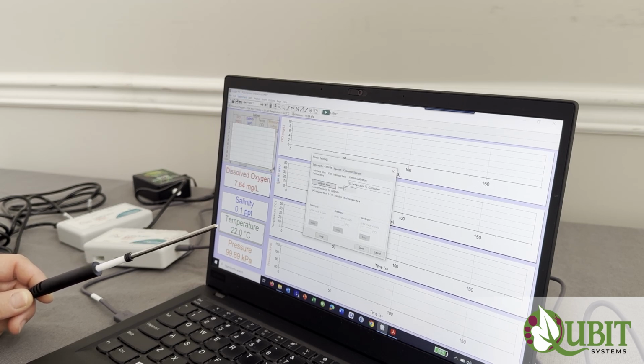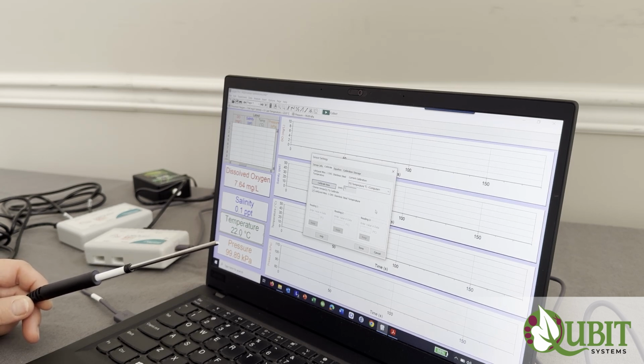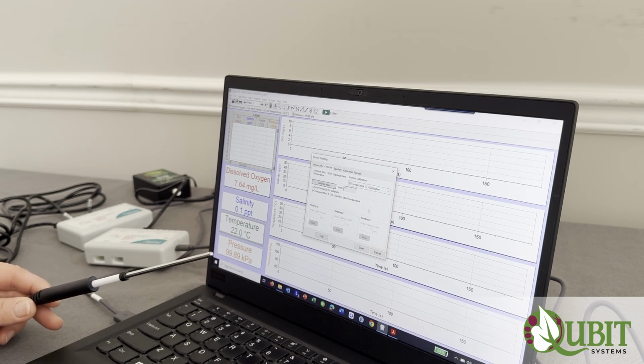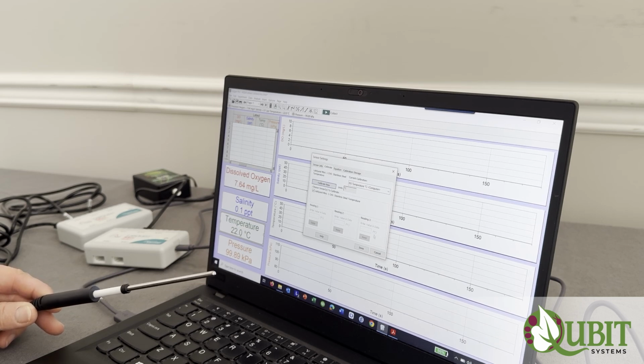And with the temperature probe, you have to do 3 readings, rather than a single reading or 2 readings. It's not a linear calibration. With the 3 readings, you would require water of 3 different temperatures and an additional thermometer or some other sensor that you know is going to provide you with an accurate reading because you'll be calibrating this probe against it. And you proceed exactly the same way by clicking on Calibrate Now and then getting a voltage reading for each one of these and then keeping it.